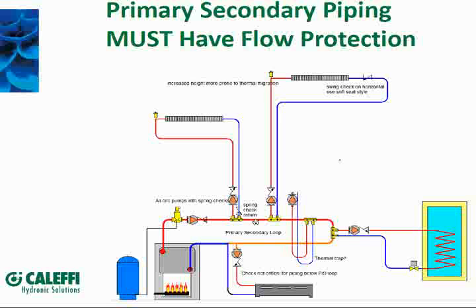It's not as critical if your piping goes down below the primary loop, since buoyancy drives things upward — takeoffs from the bottom going down won't experience thermal migration. Some installers come off the side rather than straight off the top. The straighter and taller a pipe run going up, the more it enhances thermal migration. A straight pipe to the second floor with minimal fittings or offsets will really encourage it. This is primarily where you'll see it: primary-secondary piping without adequate protection on closely spaced tee takeoffs.